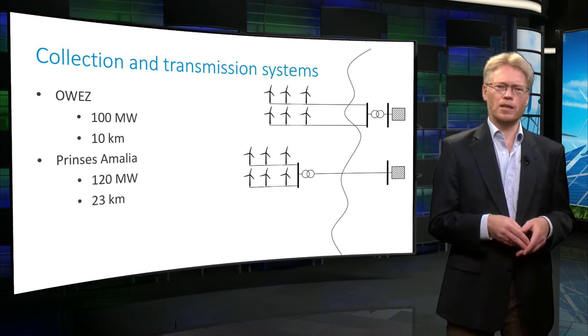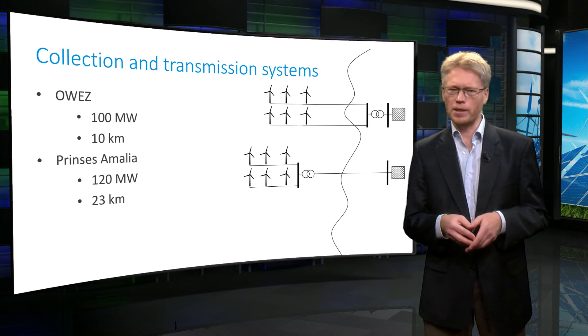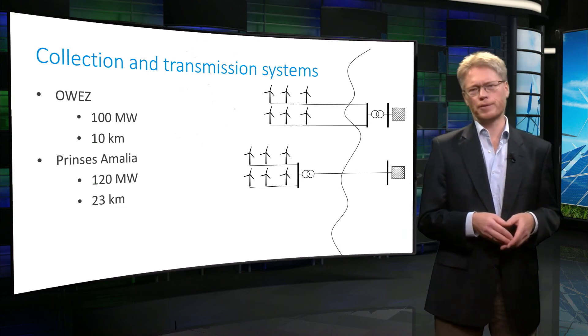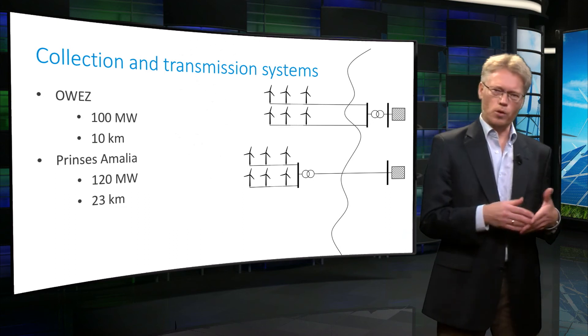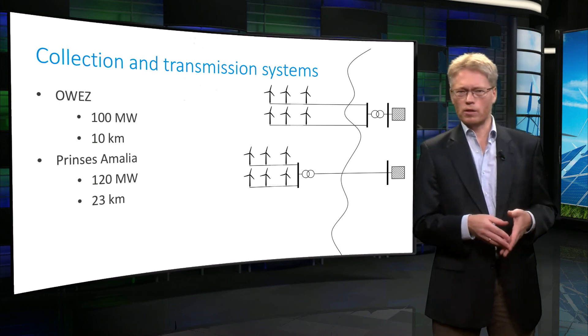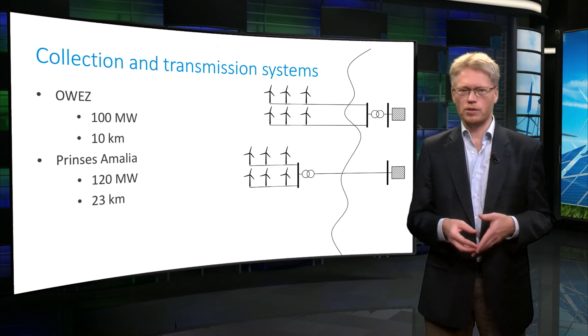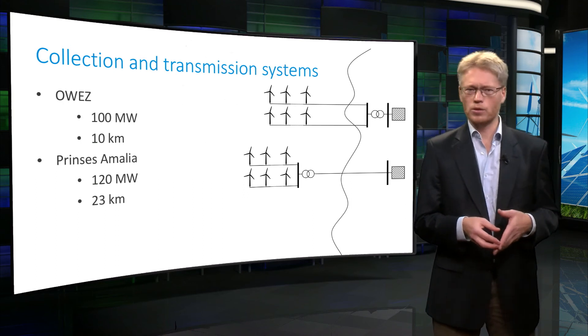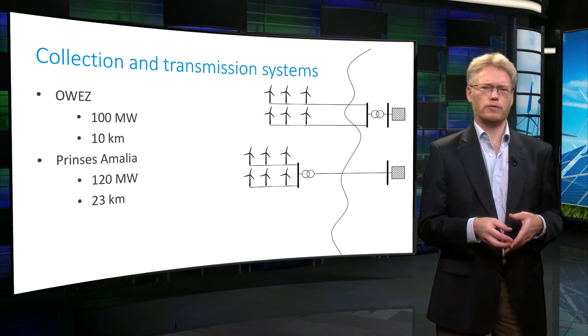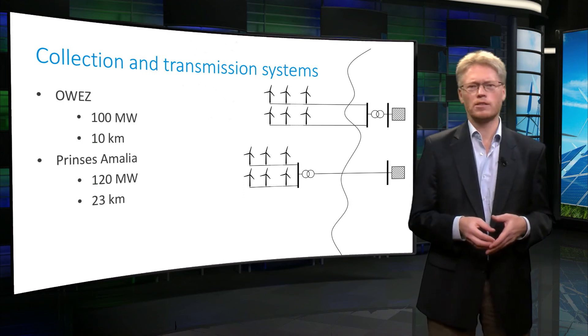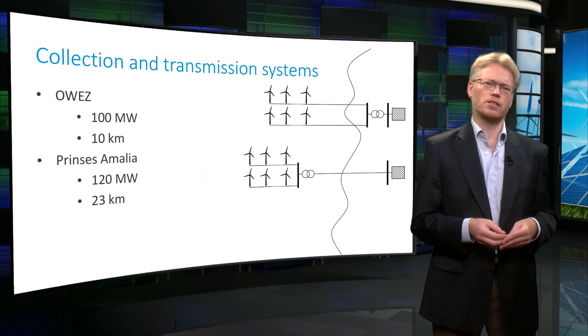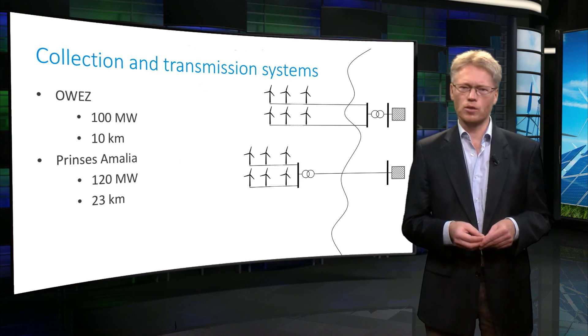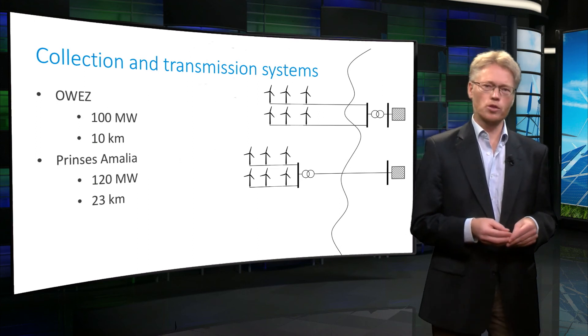The Princess Amalia Wind Farm has a power level of 120 MW and is located at 23 kilometers offshore. In this case, after the power collection, the voltage level is increased to 150 kV to transmit the power to shore. The voltage is increased to reduce the transmission losses. A higher voltage leads to a lower current, and the transmission losses are proportional to the square of the current.